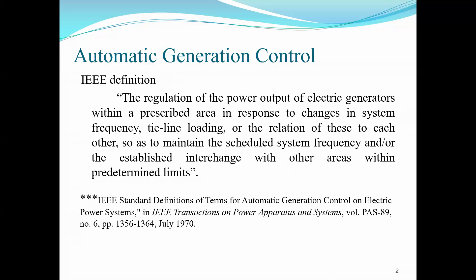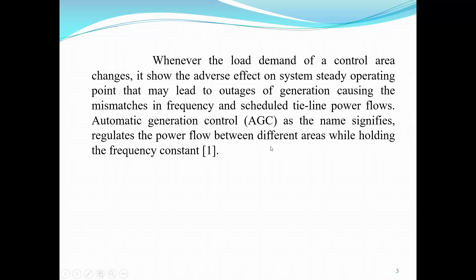As I've written here: whenever the load demand of a control area changes, it shows an adverse effect on the system's steady state operating point, that is frequency, which may lead to outages of generation, causing mismatched frequency and tie line power flows. Then AGC comes into the picture to balance the load and generation, matching load and frequency. This is called AGC, automatic generation control, or LFC, load frequency control.